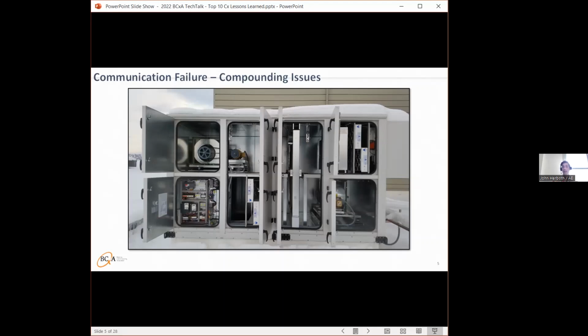Uh-oh, I have a cold front coming in, a freeze stat safety not working, and the controls provider can't be reached. More red flags just throwing up there. When I called his office, they said no one was assigned as a backup for his project, and they didn't have anybody they could transfer me to address my issues.